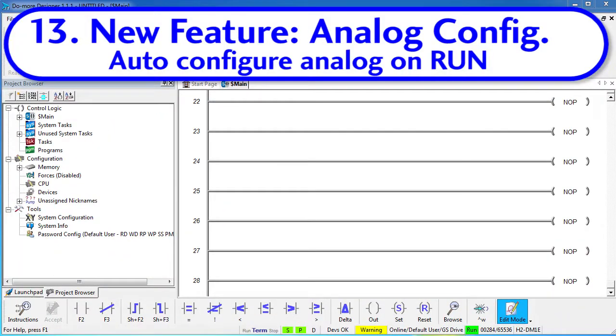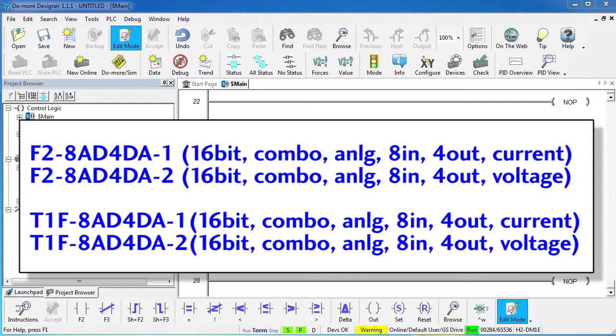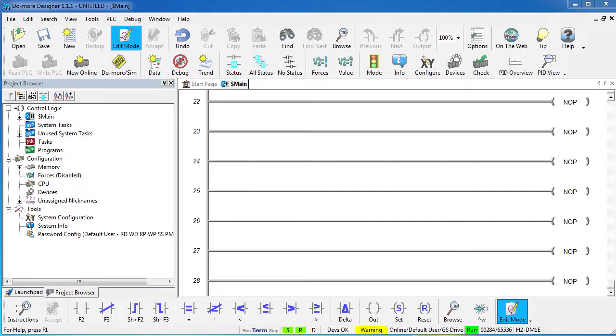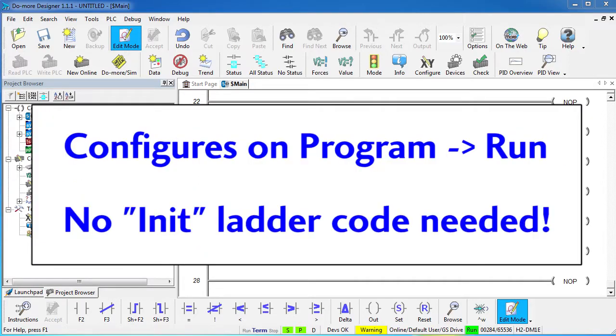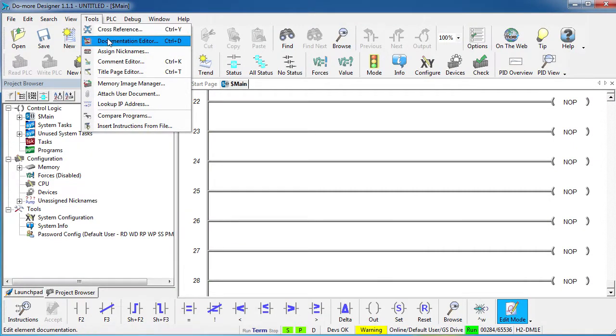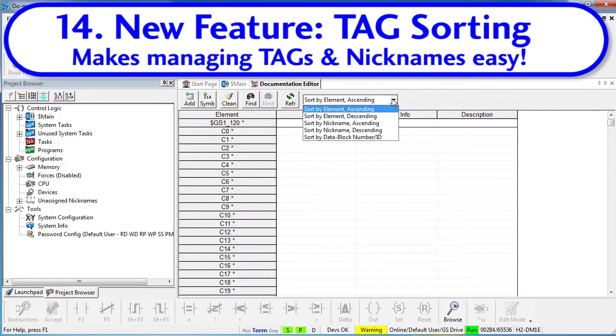Normally you would create an init routine for the more intelligent analog modules and the Terminator analog output combo modules. Now you can do the configuration via a simple dialog and eliminate all that cumbersome ladder code. And since it is stored as part of the program, it will be executed on each program-to-run transition without you having to do anything. In both the documentation editor and the cross reference, you can now sort the tables several different ways, which makes working with tags and nicknames super easy.